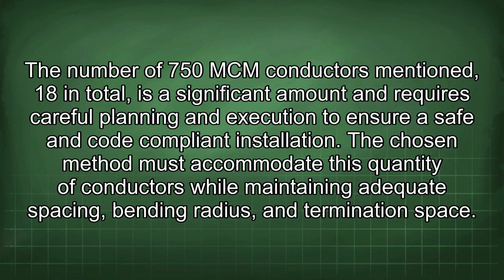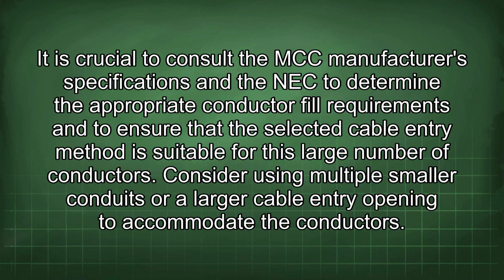The number of 750 MCM conductors mentioned, 18 in total, is a significant amount and requires careful planning and execution to ensure safe and code-compliant installation. The chosen method must accommodate this quantity of conductors while maintaining adequate spacing, bending radius, and termination space. It is crucial to consult the MCC manufacturer's specifications and the NEC to determine the appropriate conductor fill requirements and to ensure that the selected cable entry method is suitable for this large number of conductors.